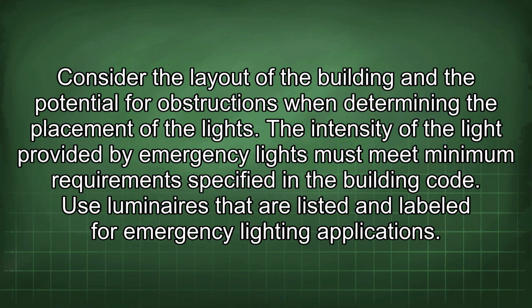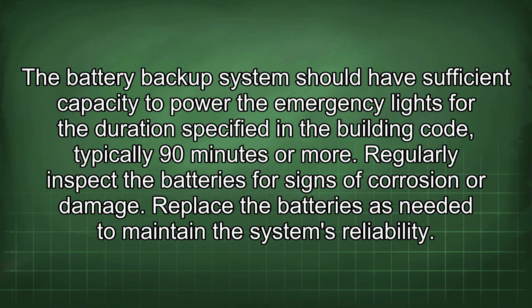The intensity of the light provided by emergency lights must meet minimum requirements specified in the building code. Use luminaires that are listed and labeled for emergency lighting applications. The battery backup system should have sufficient capacity to power the emergency lights for the duration specified in the building code, typically 90 minutes or more. Regularly inspect the batteries for signs of corrosion or damage.